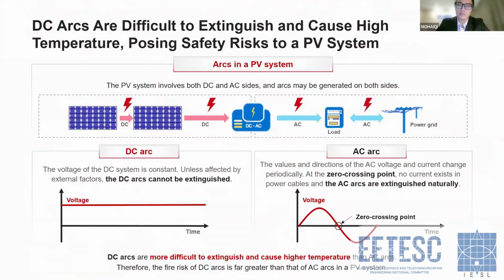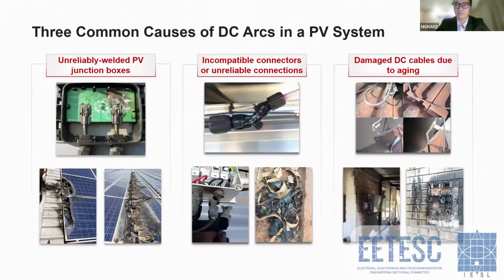And a small piece of added knowledge: why is the DC arc more important than the AC arc? Actually, an arc can happen on either the DC side or the AC side. But the AC current will automatically reduce to zero, so normally the arc is eliminated automatically, but the DC arc will not be. So for the DC side, protection is more important for us. And these are some normal reasons that cause DC arcs.